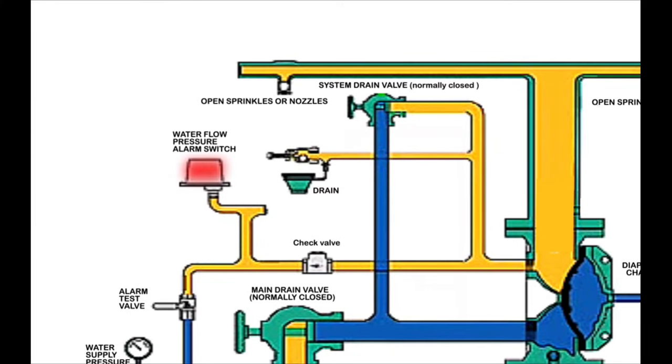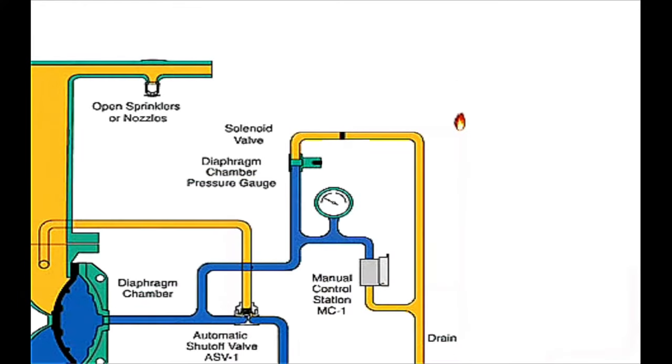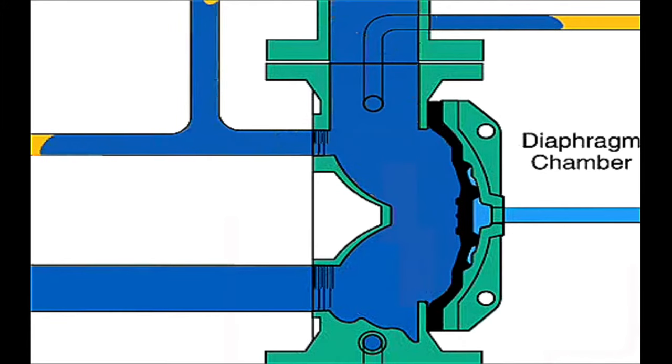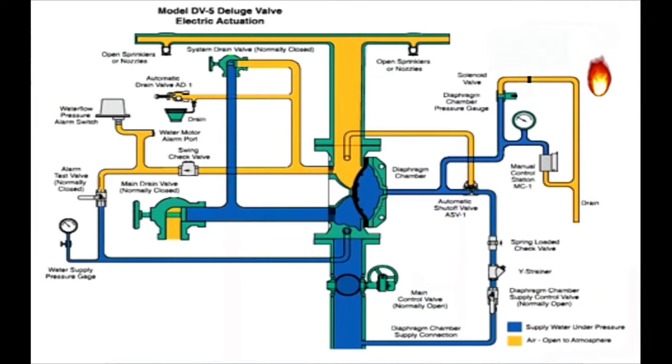Here is the high pressure switch present on the outlet of the Deluge valve, which gives an alarm signal in case of sensing supply water pressure. This alarm signal serves as an indication of the Deluge system activating and may trigger actions according to the fire and gas system. Here is the outlet of the Deluge system connected to the sprinklers or nozzles. In case of fire, when the operator presses the push button in the control room, it sends a signal to the solenoid valve, opening the path to the drain, consequently depressurizing the priming chamber and allowing water supply to push the diaphragm backward to reach the sprinklers or nozzles.